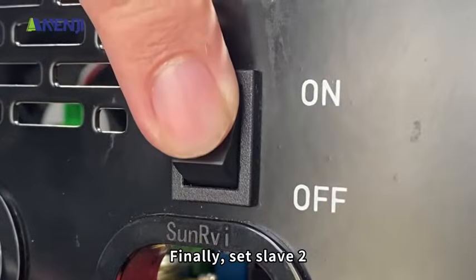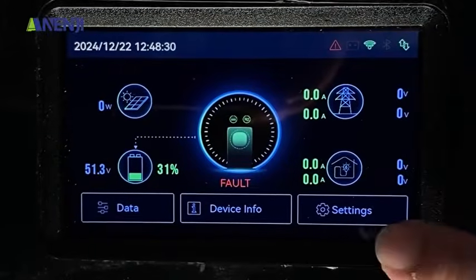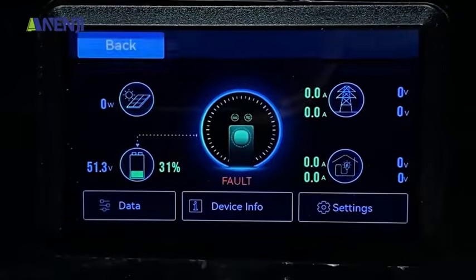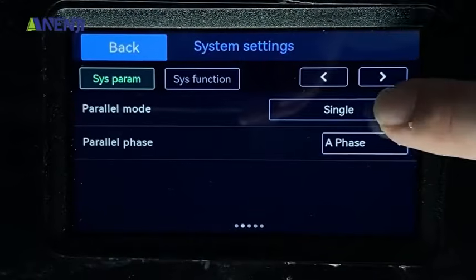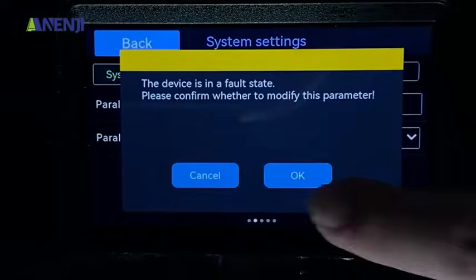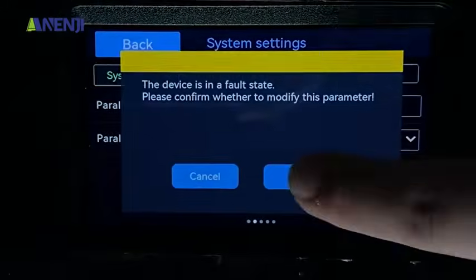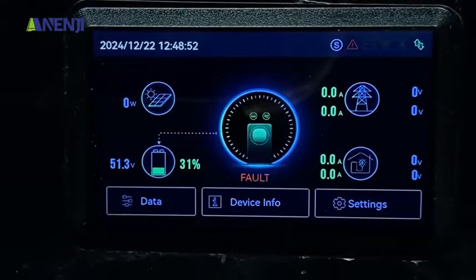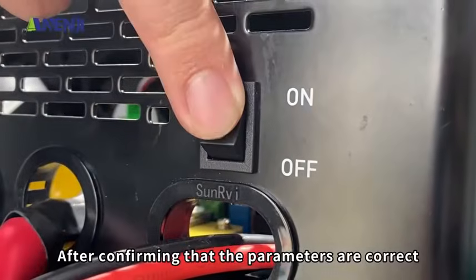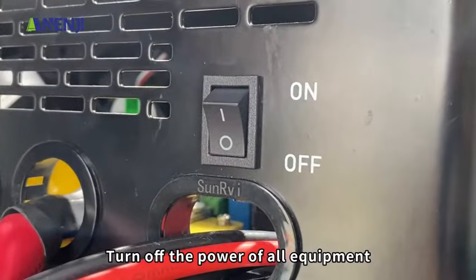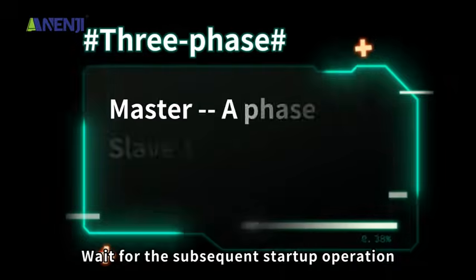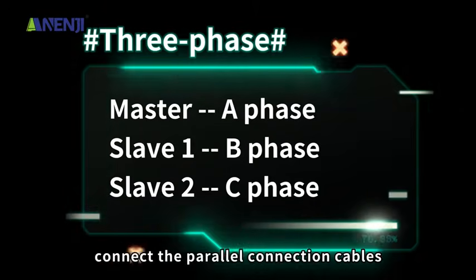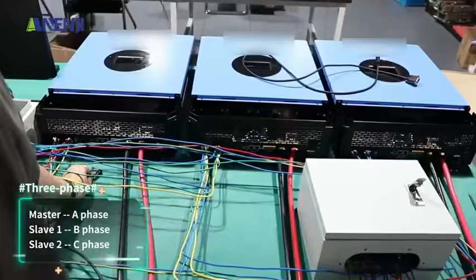Finally, set slave 2. After confirming that the parameters are correct, turn off the power of all equipment. Wait for the subsequent startup operation. At the same time, connect the parallel connection cables.